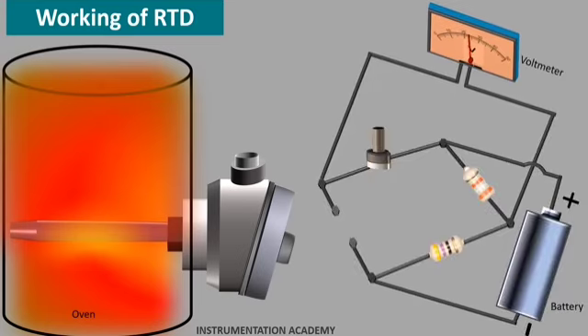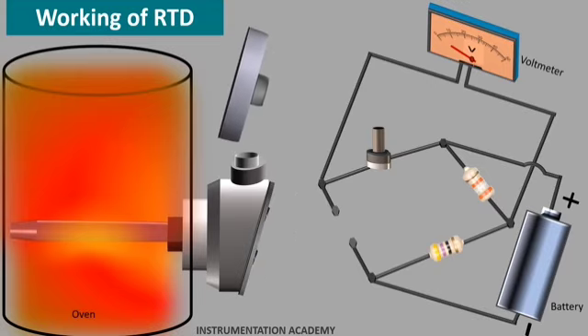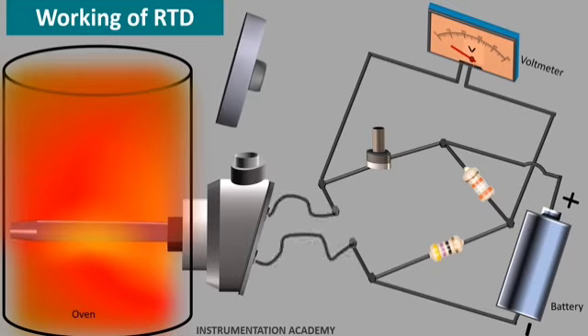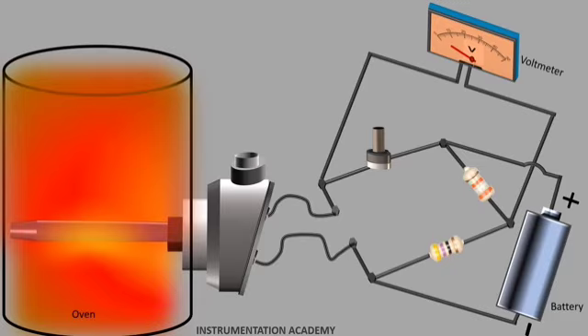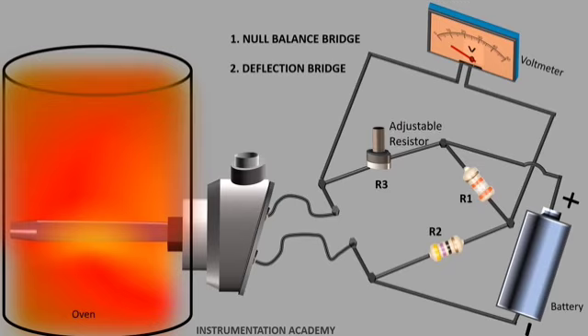These Wheatstone bridge circuits are built into the transmitter, PLC, DCS or PID controller. The RTD may be located hundreds of feet away from the bridge circuit. Two types of Wheatstone bridge circuit configurations are mainly used. One is null balanced bridge and the other is deflection bridge. In null balanced bridge, the resistors R1 and R2 are known and R3 is an adjustable resistor. The resistor R3 is initially adjusted in order to obtain 0 volt in the voltmeter. In this condition, the bridge is said to be null balanced. This would be the 0 or set point on the RTD temperature output.